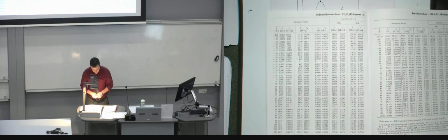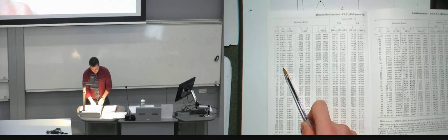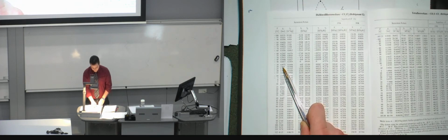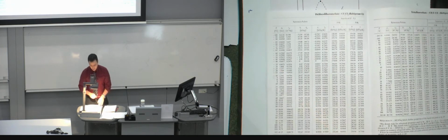That is a pressure of 1.004 bar. And in fact, if you look at this number here, you find the saturated pressure which is given to us in the example. And the saturated temperature, or the temperature which refers to this pressure, is actually minus 30.